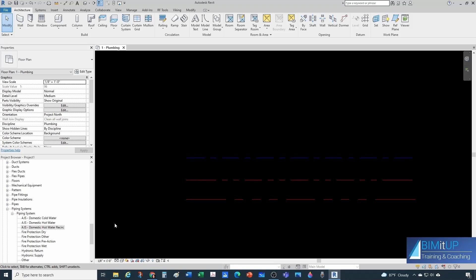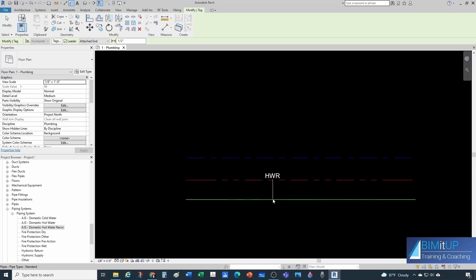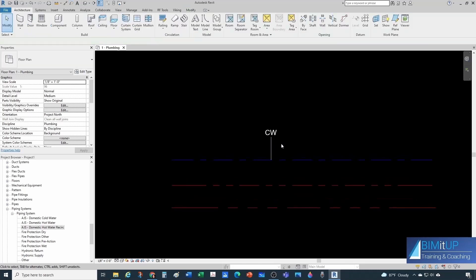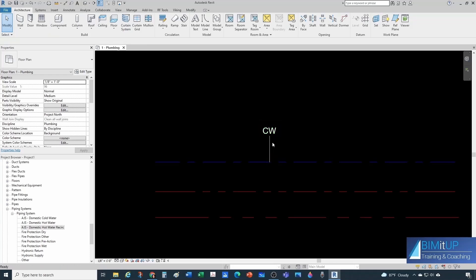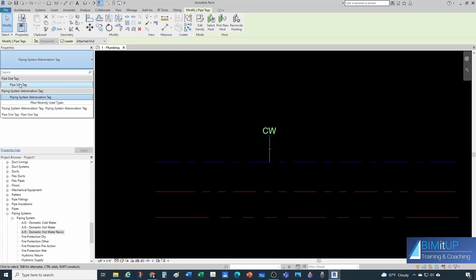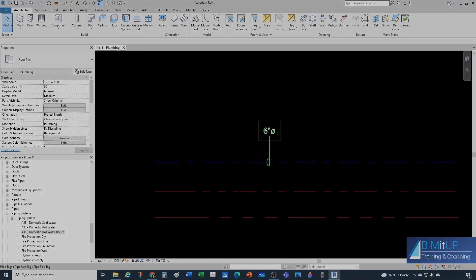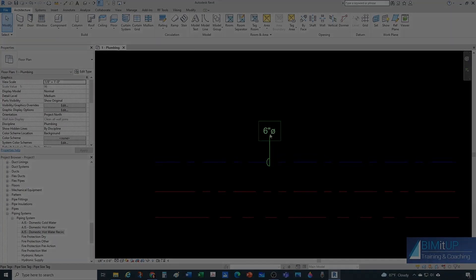Now if you want to tag your system, type TG for tag — you'll see tags appear automatically. You'll need to customize your pipe tag to show whatever you want — size, abbreviation, etc. Out of the box, Revit has a system abbreviation tag and a pipe size tag, and you can combine those two. I like showing the size — for example '6 inch' — and then the abbreviation 'CW' for cold water, so you know the size. You don't really need the diameter symbol.